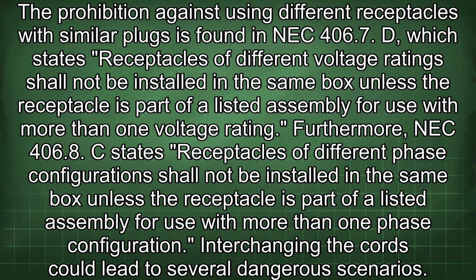The prohibition against using different receptacles with similar plugs is found in NEC 406.7(D), which states receptacles of different voltage ratings shall not be installed in the same box unless the receptacle is part of a listed assembly for use with more than one voltage rating. Furthermore, NEC 406.8(C) states receptacles of different phase configurations shall not be installed in the same box unless the receptacle is part of a listed assembly for use with more than one phase configuration.